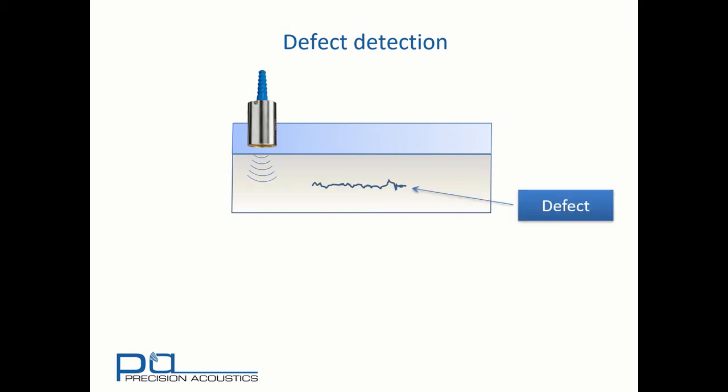We can use exactly the same principles to start to determine objects embedded within an item. This is very typically done within defect detection in non-destructive testing. So consider again a sample with some water above it, and a transducer. This time we will introduce a defect in the middle of the sample. In the initial location of the transducer, we can see the front and rear surface reflections. But if we translate the transducer over the defect, we gain an additional reflection in the middle. As previously, we can use time delays to determine where within the sample relative to the front and rear surface reflections, that defect can be located.